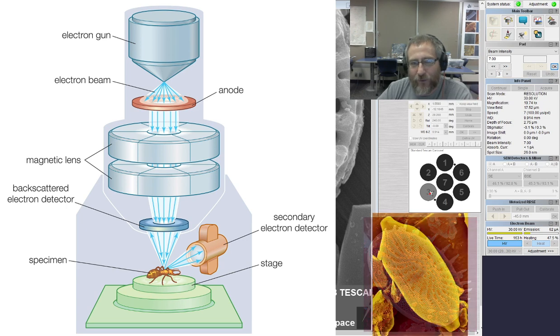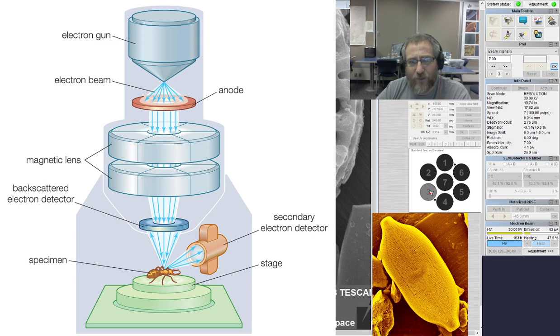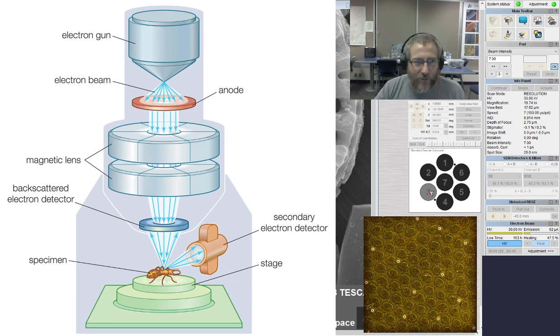And if they were moving through air, they would become dispersed. So all of this happens in a vacuum. Everything you're seeing inside the chamber happens in a vacuum. And then it works basically like a microscope after that, except the electrons are taking the place of light. You'll see there's a thing that says magnetic lenses, and that's because everything is electrons. The way you focus the beam so that it doesn't get dispersed is there's magnets, and the magnets are basically the lenses. They keep the beam going in the direction and the place that we want to put it. And this diagram has a little backscatter detector, but my backscatter detector is actually pulled out right now. It's disengaged.